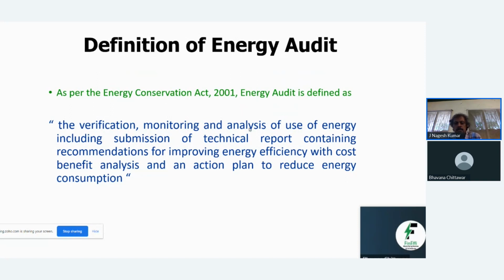As it stands today, we've more or less stopped at this point. An air analysis, a compressor audit, means FAD test, leak test, and probably suggesting pressure reduction, that's all. But if you go to the end use, where compressed air is actually used, is there an alternative way of doing the job rather than using it pneumatically?